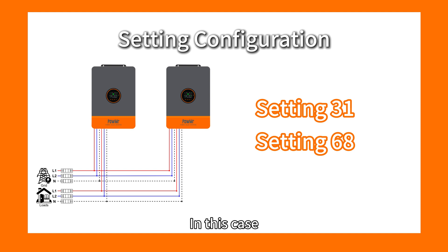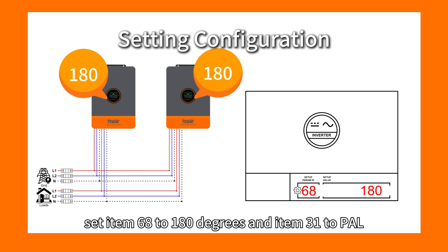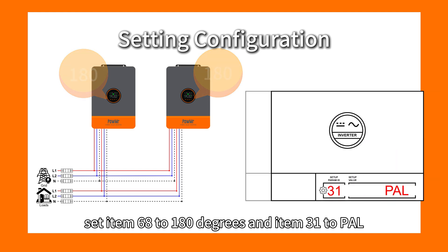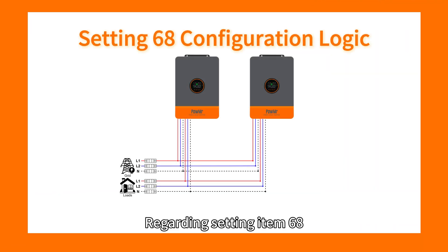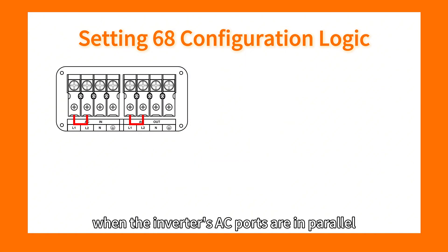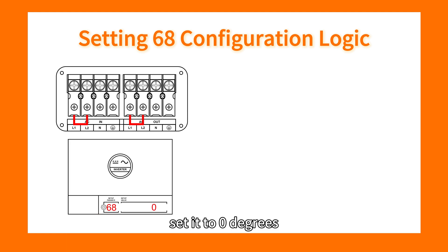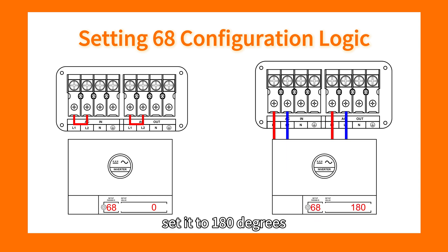In this case, settings 68 and 31 must be configured accordingly: set item 68 to 180 degrees and item 31 to PAL. Regarding setting item 68, when the inverter's AC ports are in parallel, set it to 0 degrees; when they are not in parallel, set it to 180 degrees.